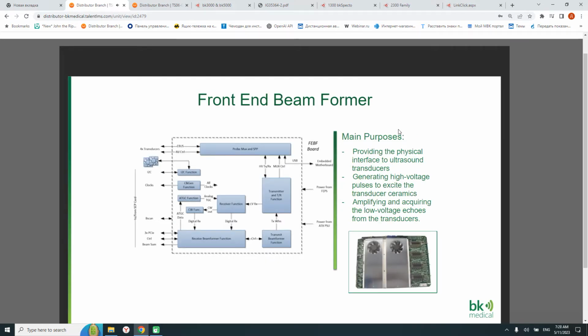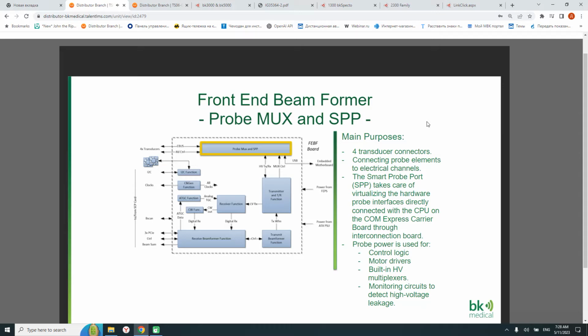The front-end beamformer board is providing the physical interface to the ultrasound transducers, generating high voltage pulses to excite the transducer ceramics, and amplifying and acquiring the low voltage echoes from the transducer. We have the probe mux and SPP function. It's connecting the probe elements to electrical channels and providing the 4 physical transducer connectors. The probe mux can be seen not only as a 1 of 4 selector, but more generally as a 192 to 768 mux. It is therefore possible to scan simultaneously on 2 or more connectors.